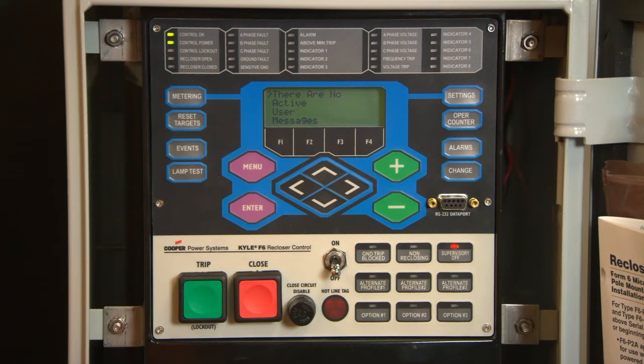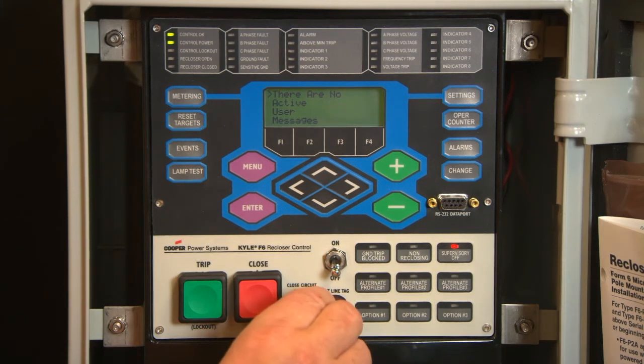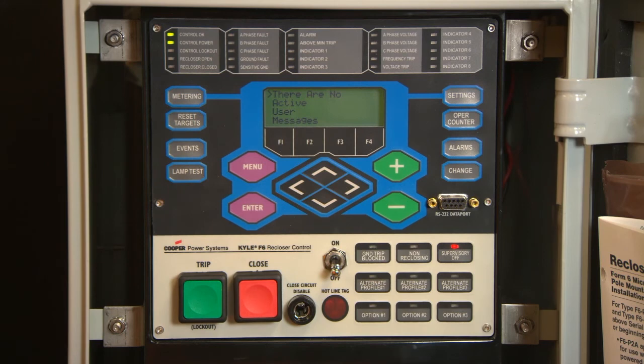Close circuit disable is a removable fuse that, when removed from the front operating panel, disables the close circuit from the control to the recloser. Removing the cartridge from the control disables all electrical closing of the recloser and provides a physical disconnect to the recloser closing circuit. As a result, the control cannot perform a close operation. The disconnect overrides all close functions and makes a remote or manual close operation impossible.